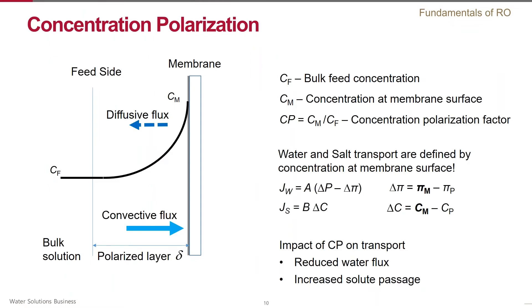A very important factor that may have a significant impact on membrane performance is concentration polarization. This phenomenon consists of the formation of a boundary layer along the membrane feed surface due to the laminar flow near the membrane, and as a result, a concentration of salt in this layer. During flow along the membrane, a boundary layer delta is formed. Two different types of flow occur in this layer: a convective flow of water from the bulk solution through the membrane, and a diffusion flow of rejected solutes from the membrane surface back to the feed flow. Since the rate of convective flow is typically higher than diffusion flow, the salts rejected by the membrane tend to accumulate in the boundary layer.